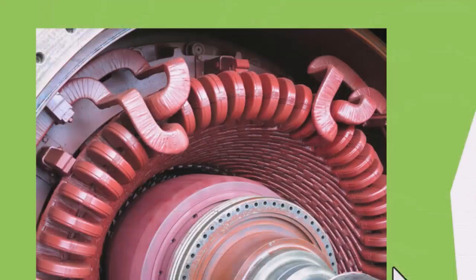The next thing we can do is to assess the gap between the rotor and the stator, that is, to test the air gap. The air gap is the space between the stator and the rotor. If it is more than what is specified, that means something bad is happening, maybe it is rubbing, we don't know. And we know that if the air gap is not uniform around the stator, it will affect the operation of the equipment, either the generator or the electric motor. So we want to be sure that the air gap is uniform.